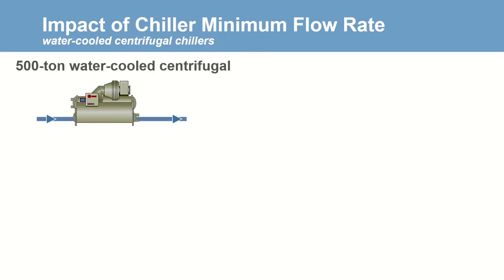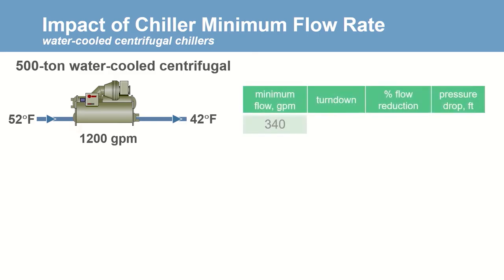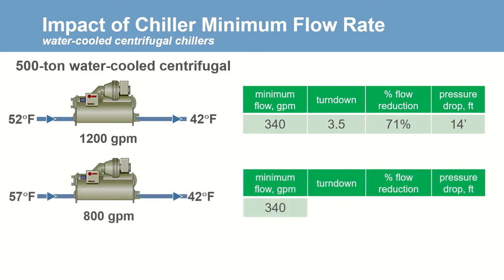To demonstrate, here's a 500-ton water-cooled centrifugal chiller. Most centrifugal chillers are highly configurable. Starting with a basic selection at 10 degree delta T and design flow of 1200 GPM, the minimum flow for this specific chiller is 340 GPM, pressure drop is about 14 feet, and this provides a 3.5 to 1 turndown, or a 71 percent flow reduction. Taking this exact same chiller but running at a 15 degree delta T, the design flow rate reduces but the minimum stays the same, resulting in a turndown of 2.3 to 1, or only a 57 percent flow reduction.